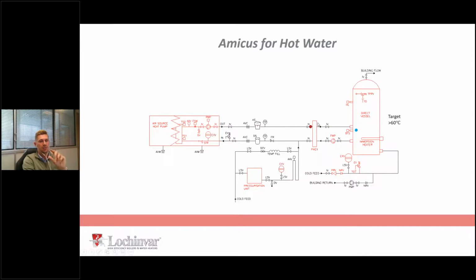The secondary side operates, and we size the plate heat exchanger in such a way that we only lose 1 degree across the surface of the plate. So we flow in at 63, we flow out at 62 on the potable side. The top 2/3 of the volume is in excess of 60 to distribute off to your building. It then returns at 55, floods through your return into your plate heat exchanger, and then basically gets topped back up to 60 to then be redistributed to the building. So from a hot water point of view, it's very possible.